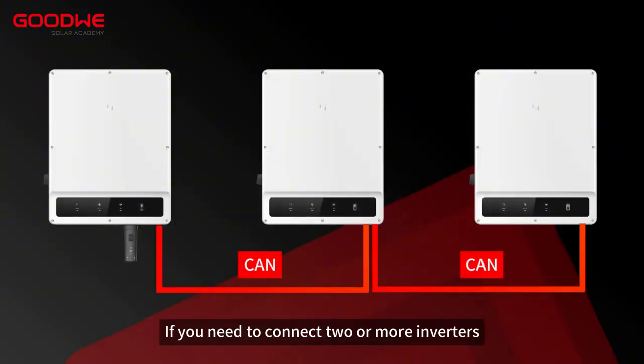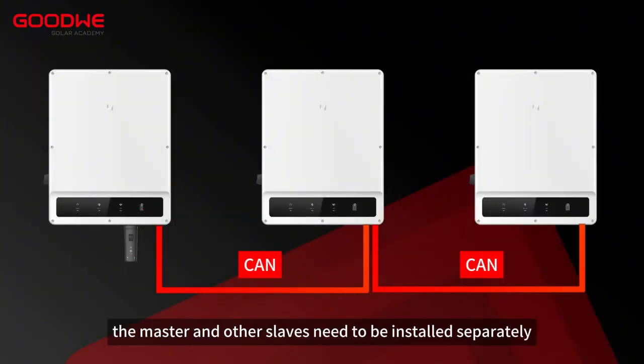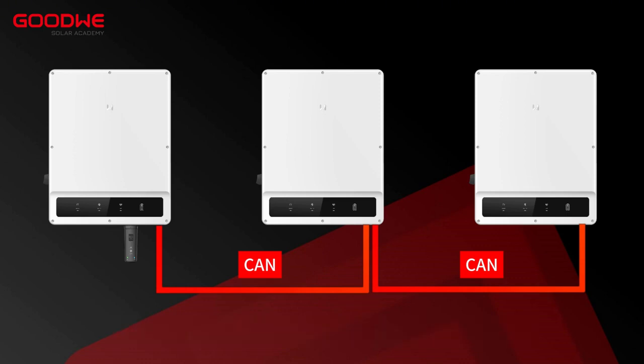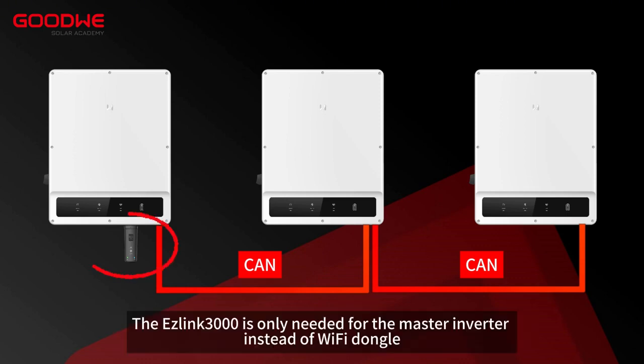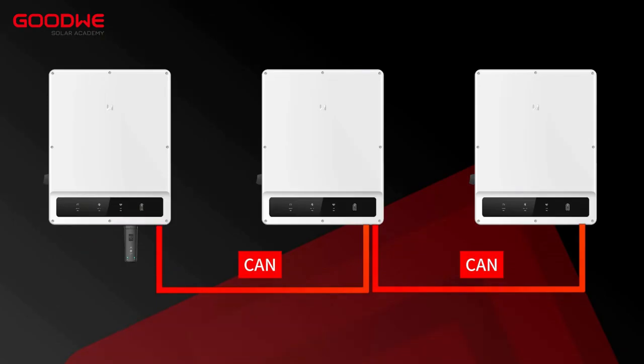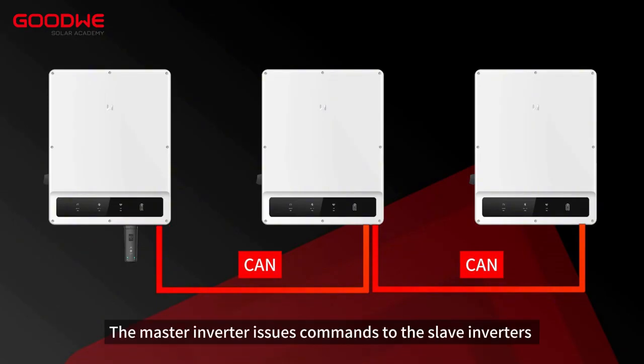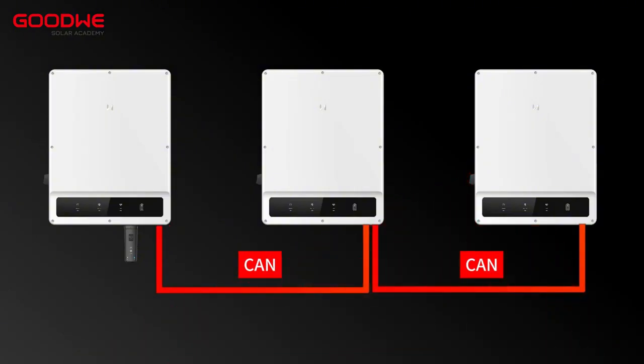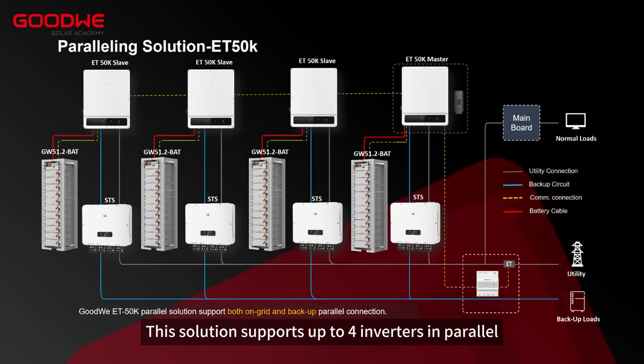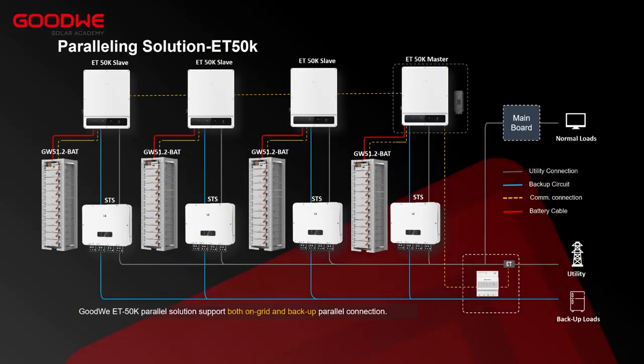If you need to connect 2 or more inverters, the master and other slaves need to be installed separately. The Ezlink 3000 is only needed for the master inverter instead of Wi-Fi dongle. The master inverter issues commands to the slave inverters via the communication cables. This solution supports up to 4 inverters in parallel.